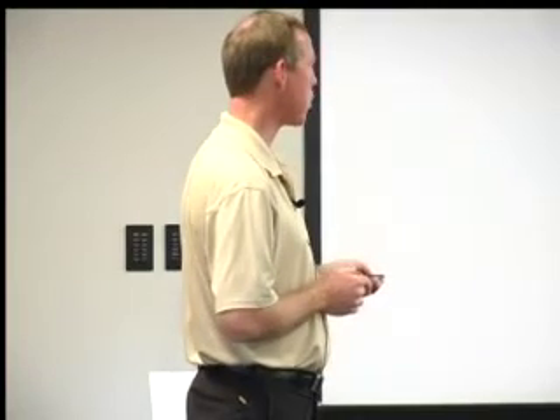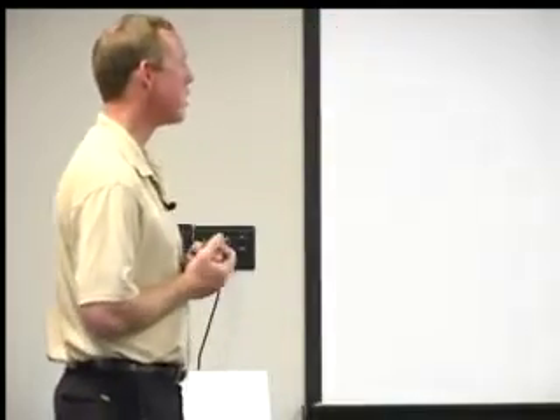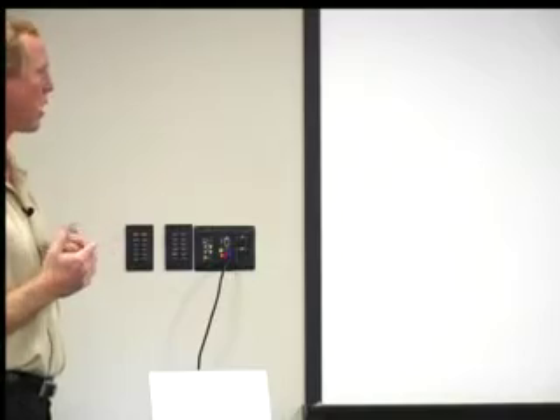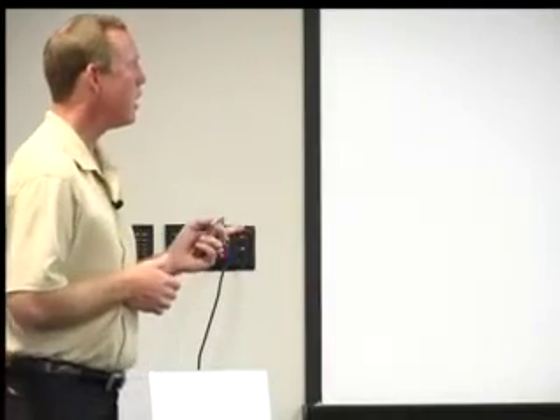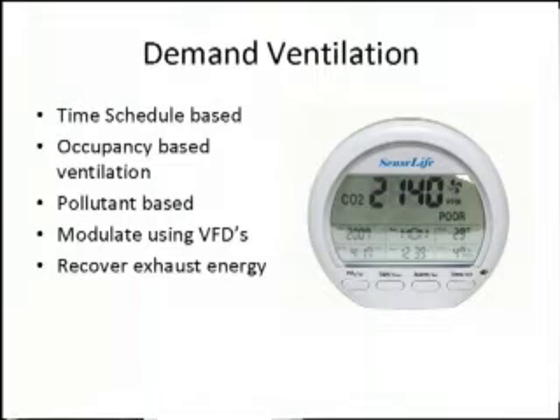And what happens next? We've got unhappy people. We face this every day at UCF, trying to get the ventilation right so that we're not having to put in artificial warming means to keep the place warmed up. But you can't always do it, and we're going to talk about how you can maybe warm things up. Besides unhappy people, we also have humidity concerns when this happens. As the temperature drops in the space and the water content remains the same, the relative humidity rises. It's another issue we face when we lose our heat load all of a sudden. So we're going to look at ways to prevent overventilation, and also what we can do when we can't prevent it.